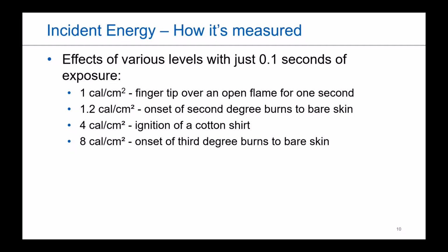And so 1 calorie per centimeter squared is basically if you were to take your fingertip, put it over an open flame of like a candle and just hold it there for 1 second. So the amount of heat that you're feeling there will be the equivalent thermal energy to 1 calorie per centimeter squared.